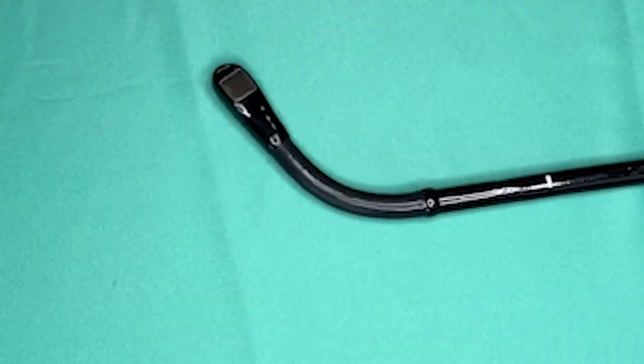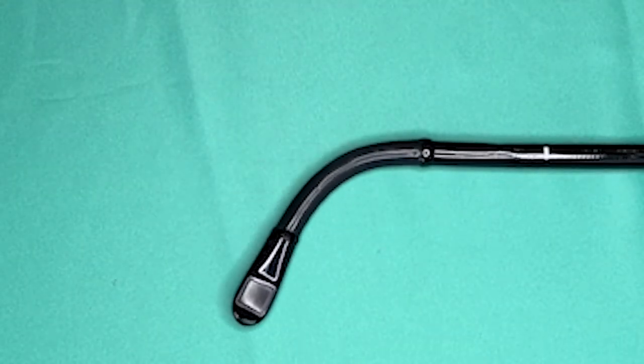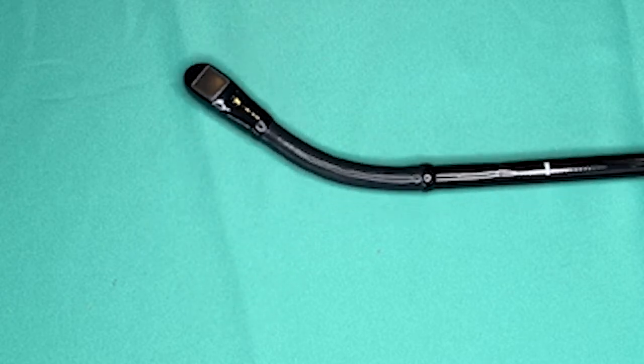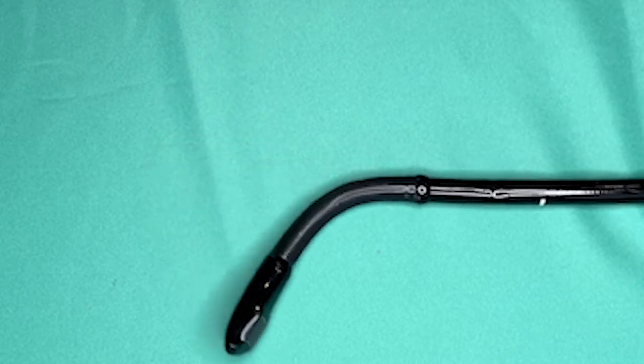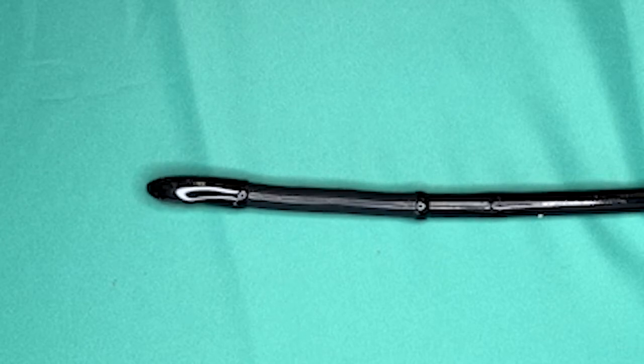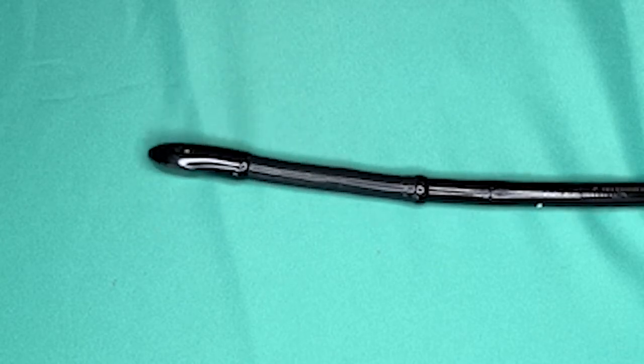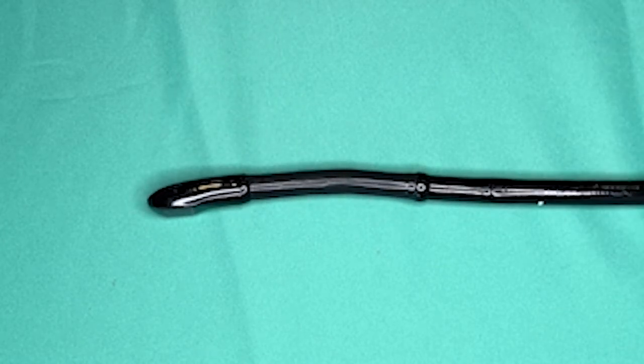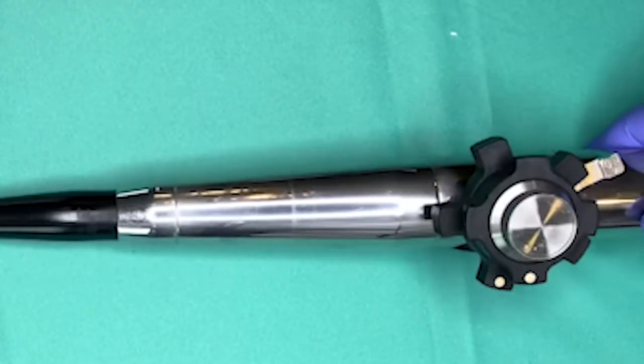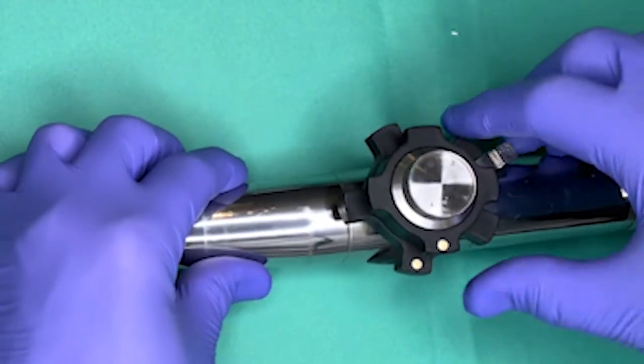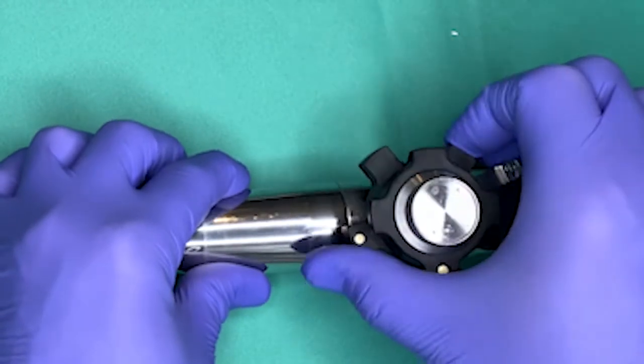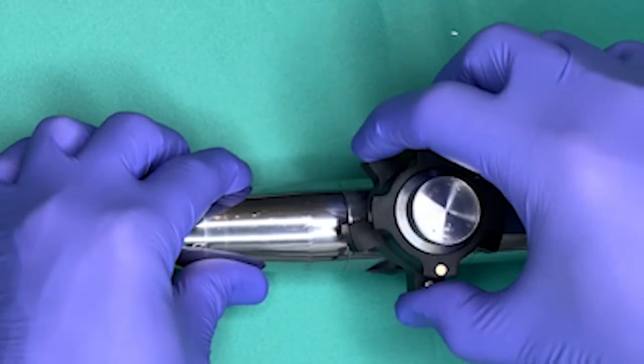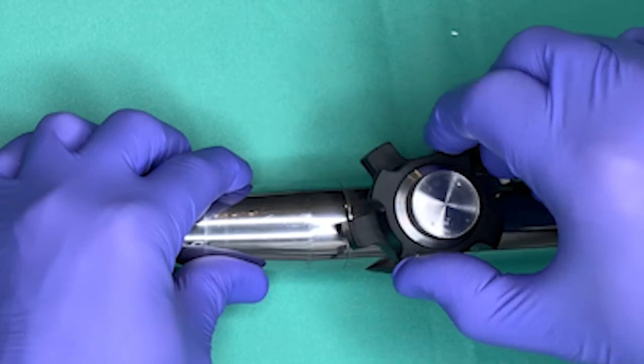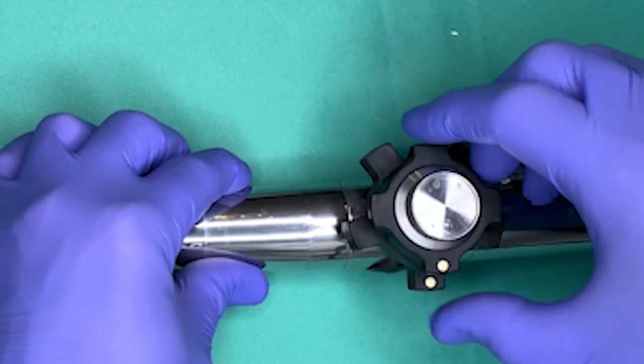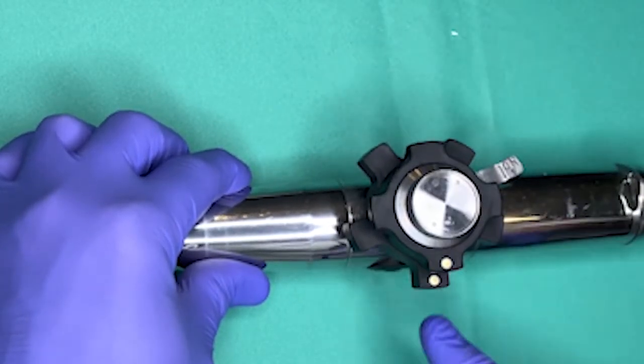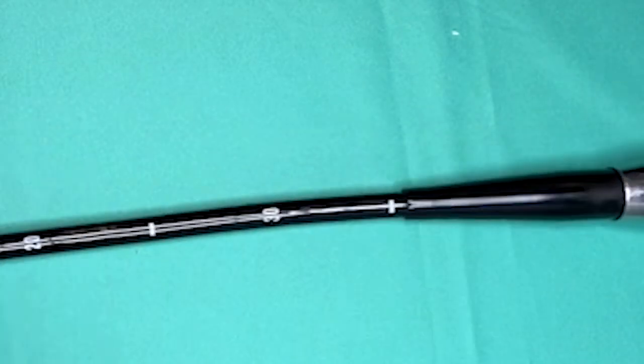To begin, operate the angulation controls in all directions, feeling for tightness of movement and observing the distal tip for smoothness of movement. Also get a feel for how much the control knob turns in each direction before the distal tip moves. This is the amount of play in each direction. Excessive play in any direction usually results in decreased range of motion and indicates a need for an angulation adjustment.